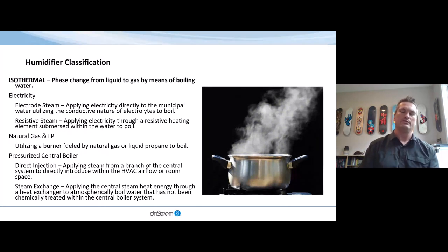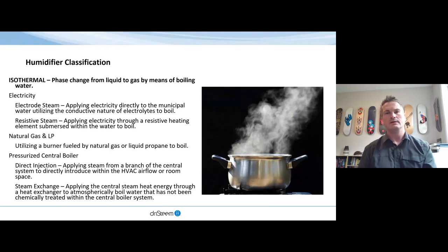Natural gas and liquid propane are another form of energy that can be utilized through a burner to boil water as well. And then pressurized and central boilers and the distribution network of that can be directly injected into the air supply through branch networks of the HVAC, or it can be applied through a steam exchange process. This is taking that heat energy from the central boiler through a heat exchanger and then boiling water that has not been treated, that typically is found within the centralized steam production, and applying that atmospheric steam then into the airflow of the HVAC ducted system.